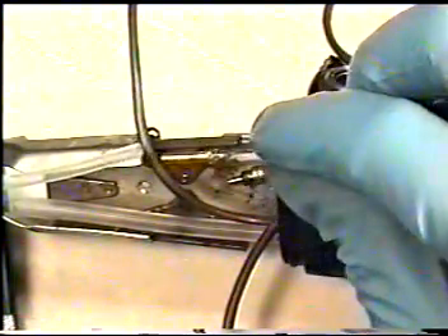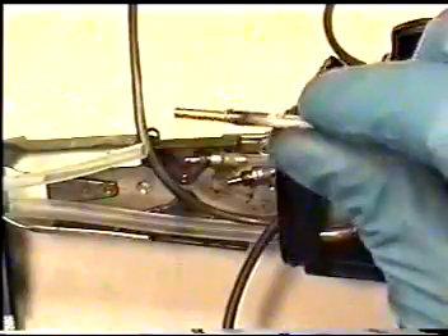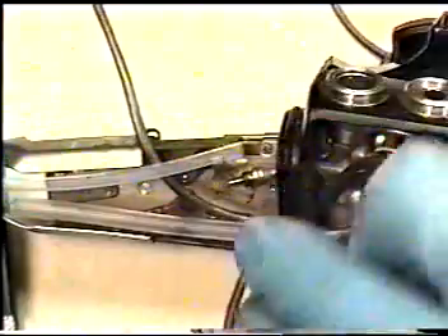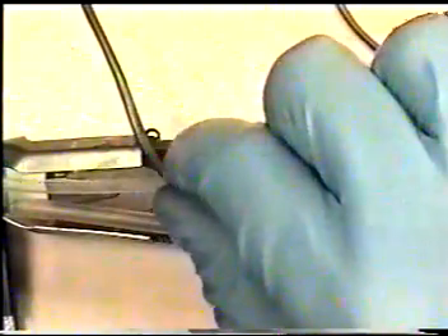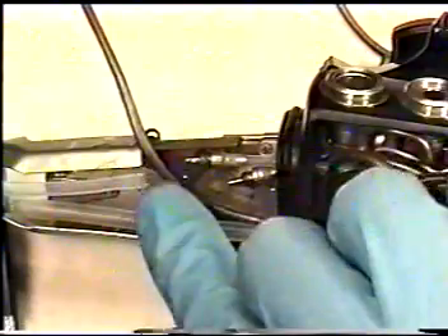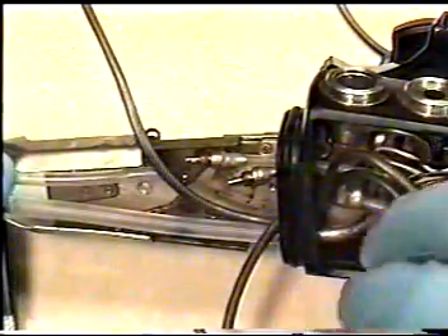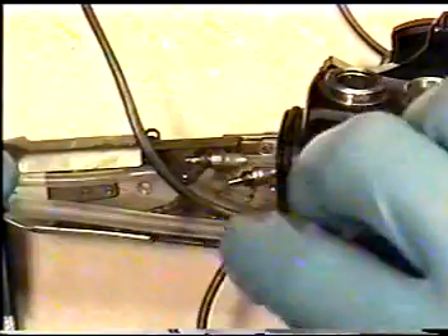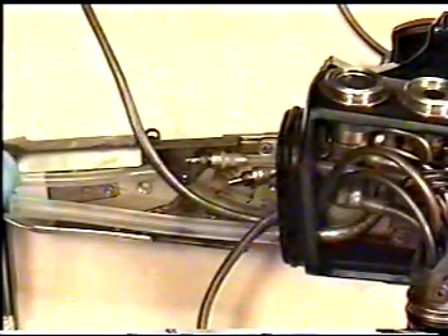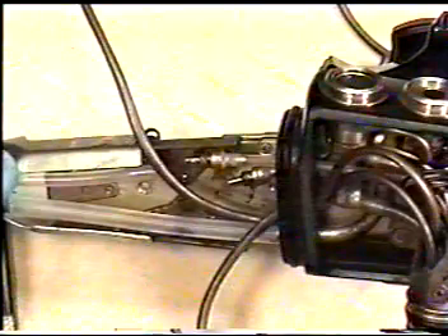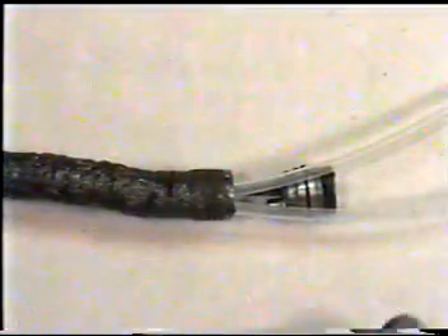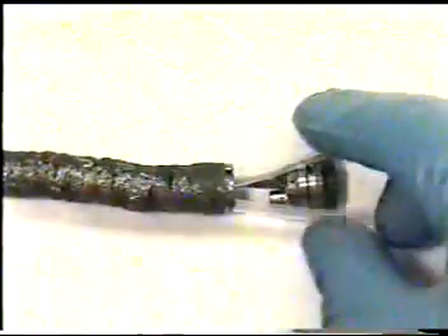Once the tube has reached the body section, you can remove the old light guide and put it to one side. This will allow us to pull through our new light guide tube back through the insertion tube down to the distal end. Repeat the same for the second light guide bundle, pulling down light guide bundle through insertion tube into body section. At the distal end, both our plastic tubes are now ready to pull through our new illumination light guide bundles through the bending section insertion tube from the body.